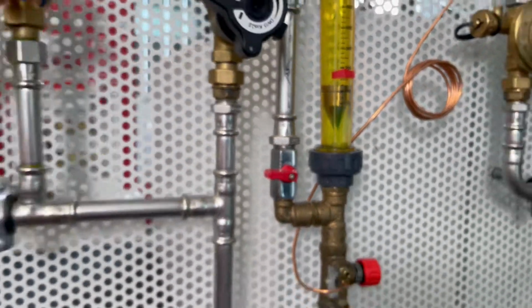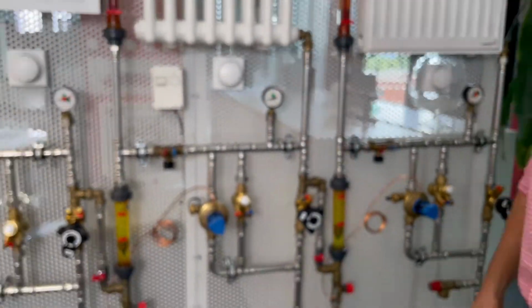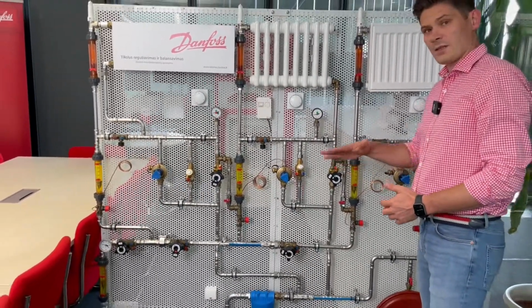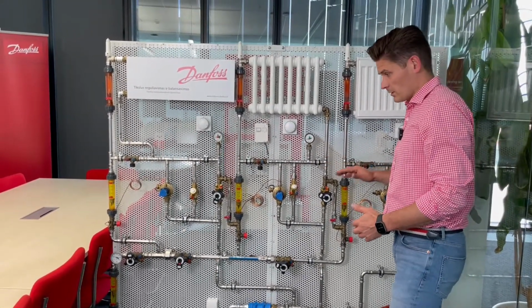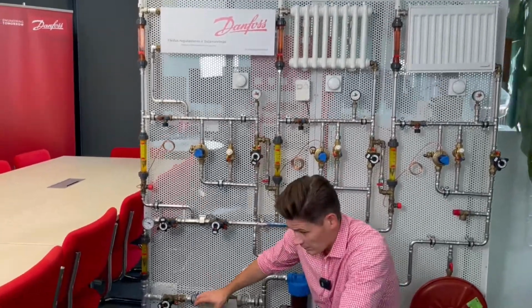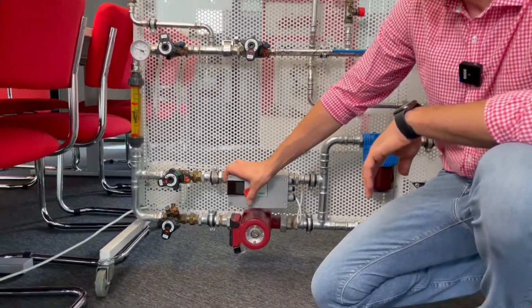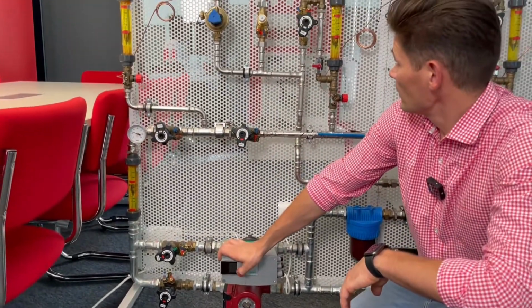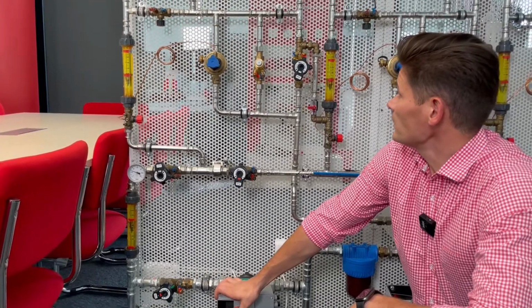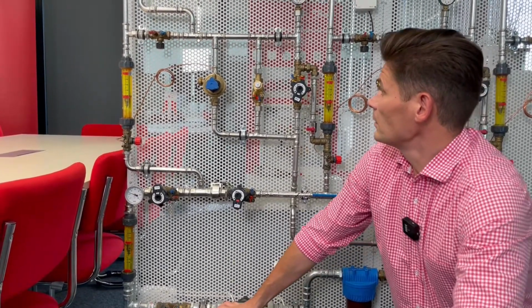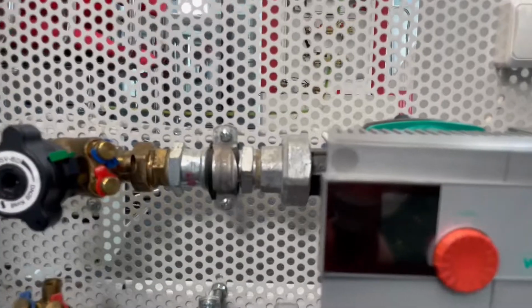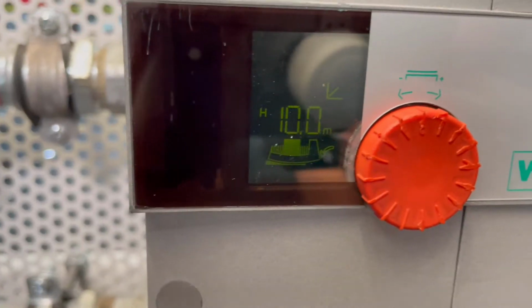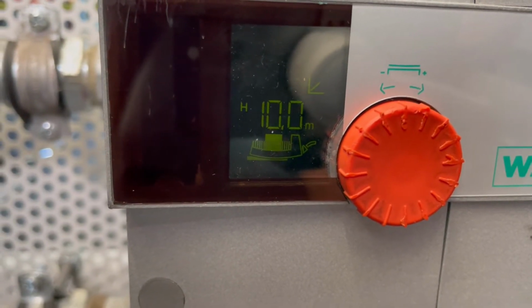So to make the experiment fair, I need to increase the pump head with a different setting to have the same flows in each riser, 200 liters. So I will now increase the pump head, just like this, looking at the risers to have the same 200 liters for each riser. Okay, 200 liters for each riser. Let's check the setting of the pump. How much do we have now? It is okay, it is 10 meters. It was 5.1 at constant curve, and at variable curve we have 10 meters.